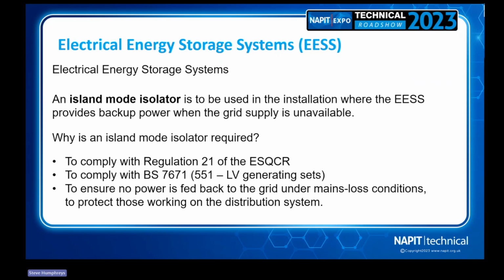So basically, to comply with Regulation 21 of the ESQCR regulations, we've got to make sure that we are not backfeeding any power in island mode back to the actual distribution system, because that could be a linesman working on the grid. Your local generation is feeding backwards and actually going to do someone a mischief that's working on the distribution system. So this is all about parallel supplies. So that is a legal requirement. And also we're complying with BS 7671 and especially section 551.